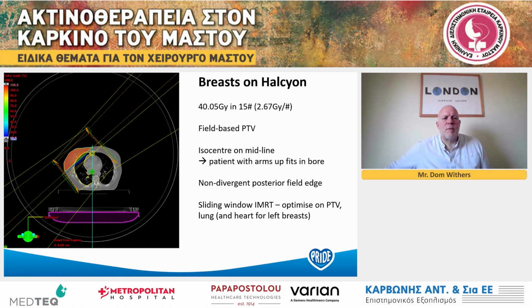And the reason we do this is because the scan only reaches up to just under the chin or under the nose, depending on what we are treating. And we cannot see the elbows in the CT scan. So we do not know where the elbows are. However, when we are planning, there is this big white circle here, which represents the position of the bore of the Halcyon machine. And inside by 2.5 centimeters is a little warning circle as well. And so you must keep the couch and the patient inside these circles. Otherwise, you cannot treat the patient because the machine needs to know if the patient is going to hit the bore.